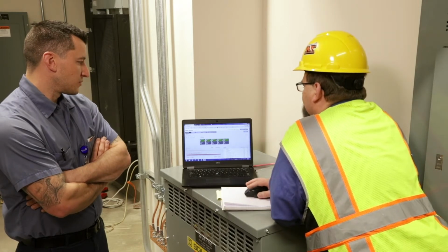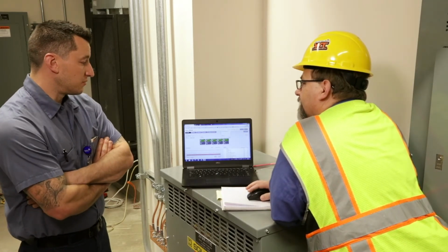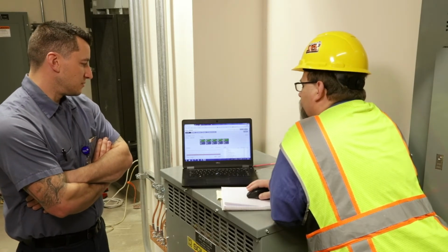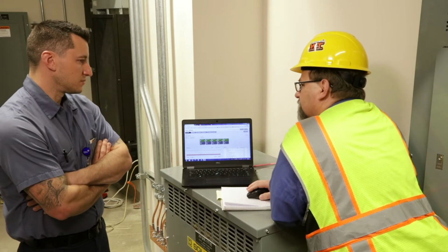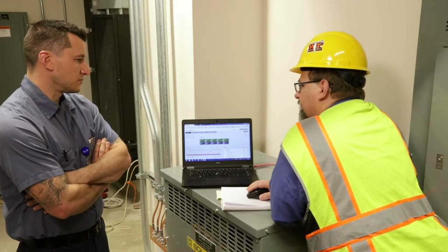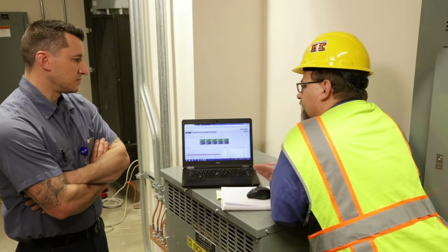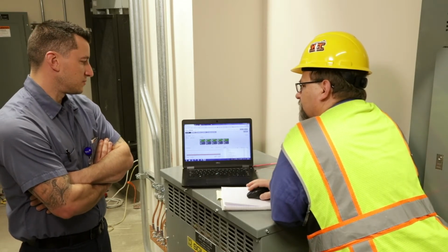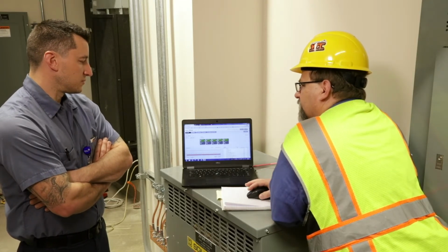Other questions, sir? What about overriding the outside lights if we wanted them on for whatever reason? You could set them in a group and you can adjust the group status. You could create a new event and just for that one day do the override for the event, so like on a schedule. Or you can go to the individual outside lights and control them individually and just turn them on, and then the next scheduled event will pick them up to where they need to go.